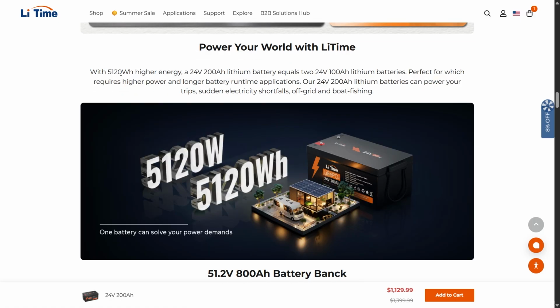With 5,120 watt-hours of higher energy, this 24-volt 200-amp-hour lithium battery equals two 24-volt 100-amp-hour lithium batteries. And the best thing is you can output at a higher amperage, which gives you higher wattage output. You can output 5,120 watts continuously. You can only get half of that from a 24-volt 100-amp-hour battery usually.